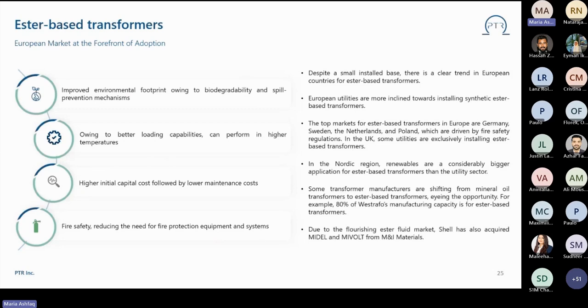If we talk about some of the major properties of these ester-based products, on top of it, it is biodegradable and non-toxic, and these two factors basically support the notion that ester is sustainable, climate and environment friendly. Similarly, its thermal aging property is much better than mineral oil, giving it a longer lifespan. So if you have a transformer with ester oil and another with mineral oil, the lifetime of the ester oil based transformer will be much more than the conventional mineral oil based transformer.